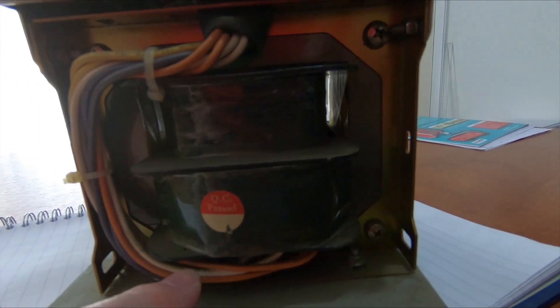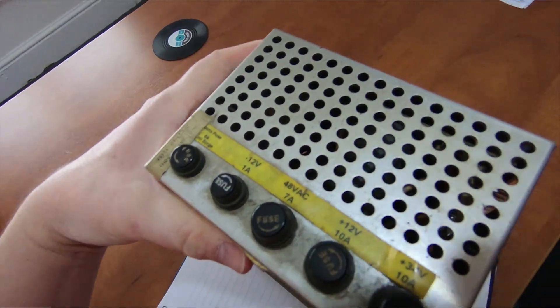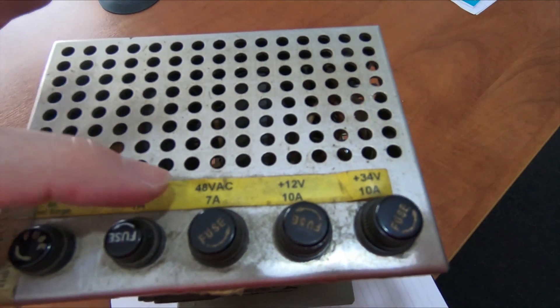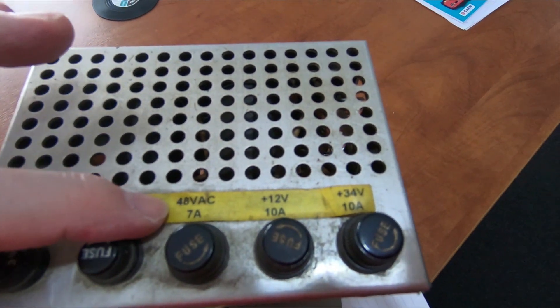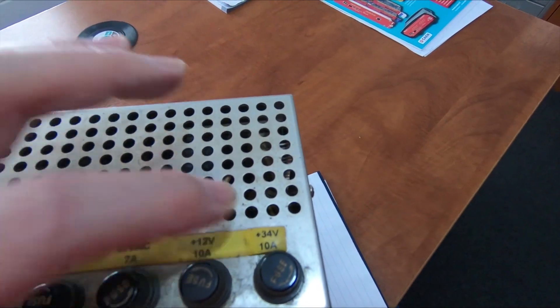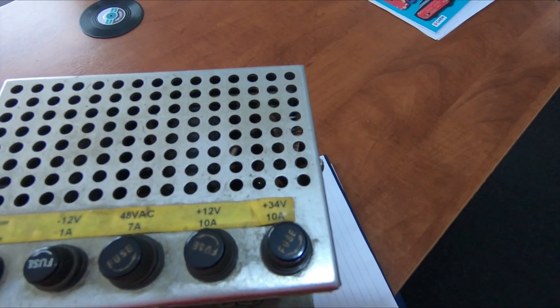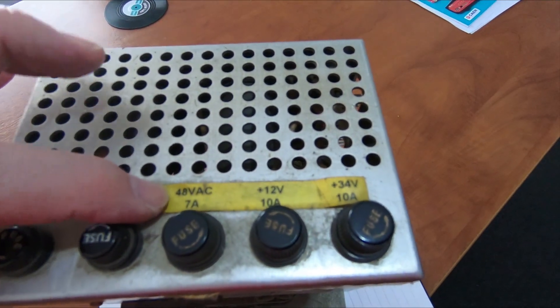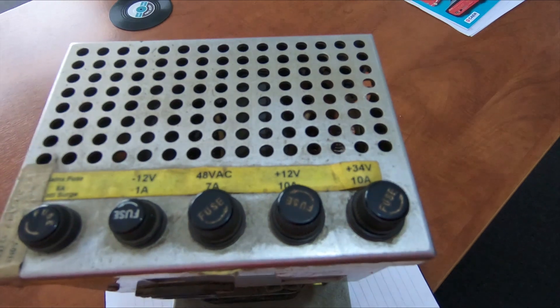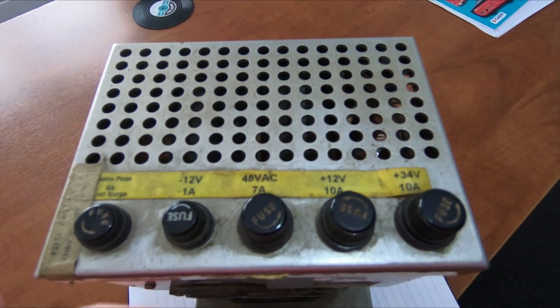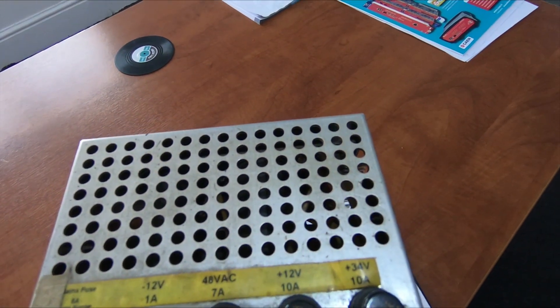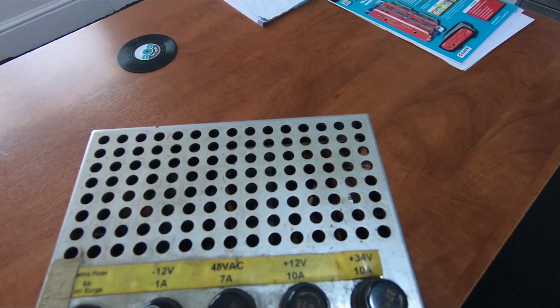There will be multiple voltage taps coming off the transformer winding. On the top of the supply we can see the output voltages: minus 12, plus 48 volts AC, plus 12, and plus 34 volts. The 48 volts AC will come straight off the windings.